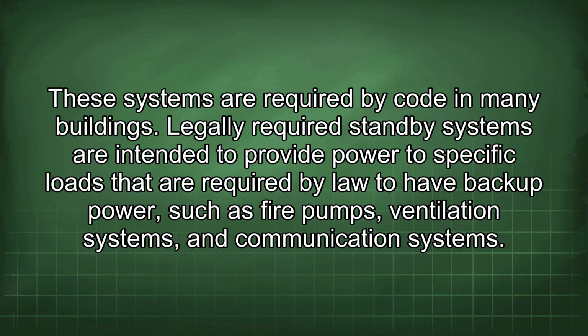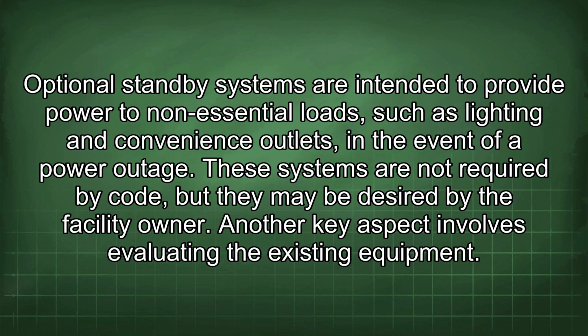These systems are required by code in many buildings. Legally required standby systems are intended to provide power to specific loads that are required by law to have backup power, such as fire pumps, ventilation systems, and communication systems. Optional standby systems are intended to provide power to non-essential loads such as lighting and convenience outlets in the event of a power outage. These systems are not required by code, but they may be desired by the facility owner.